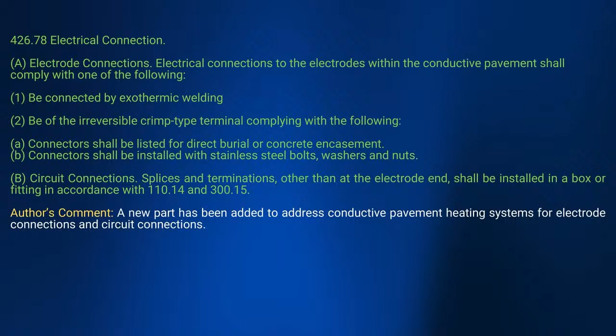Then it gets into your GFCI protection. Now, once again, this is why I'm telling you 210.8(F) doesn't apply, because what does this have to deal with? This is an engineered design system. And it tells you GFCI protection shall be provided for all 125 volt, 15 and 20 amp single phase branch circuits supplying equipment installed on the conductive pavement. And then they start telling you about the material testing that is required, which is what we talked about earlier.